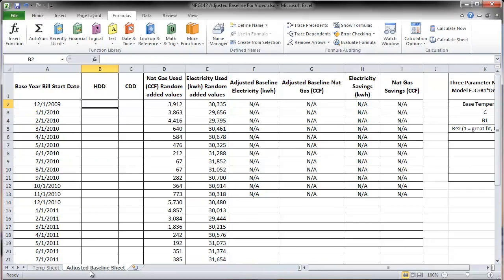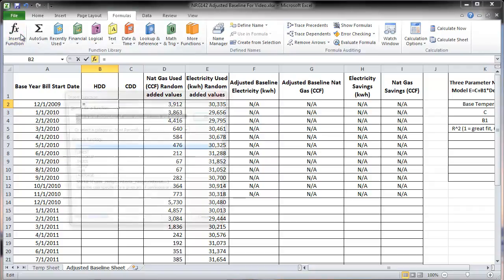Now that we've covered heating degree days, we're going to the adjusted baseline sheet. One goal of an adjusted baseline is to adjust the electricity or energy use via a model — for example, if you have a very hot or cold summer. We have our billing dates, and we want to calculate the heating degree days and cooling degree days between those billing dates. For cell B2, we want to calculate the heating degree days between December 1, 2009 and January 1, 2010.